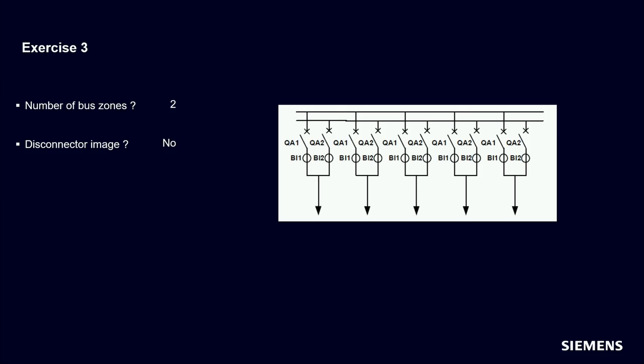There is no disconnector image, because you can't switch CTs by disconnector positions to different bus zones. Number of bays: look carefully. From the customer's point of view, it looks like 5 bays. But here we really need 10 bays, because we need 1 bay per pair of CT and circuit breaker in each bay. So from the customer's point of view, the 2 bays are combined into only 1 bay, but for our busbar protection, we really need 10 bays.